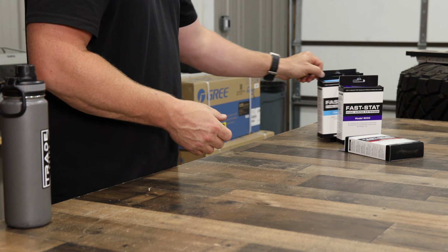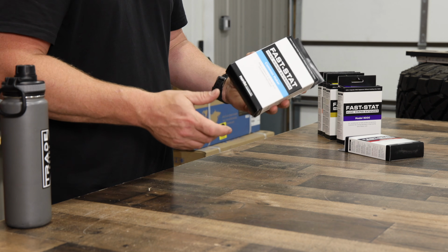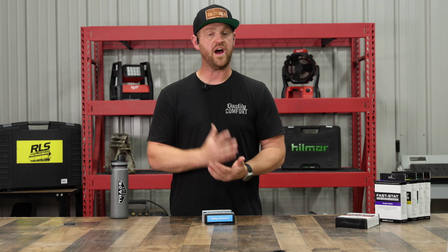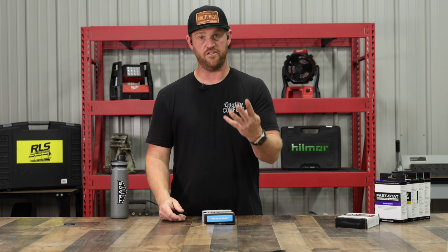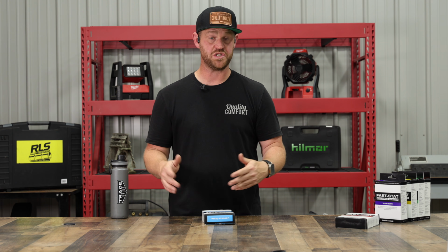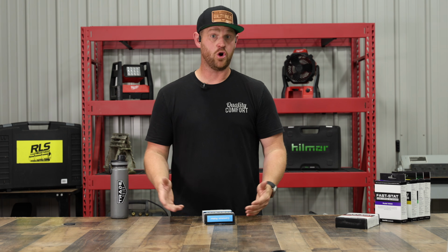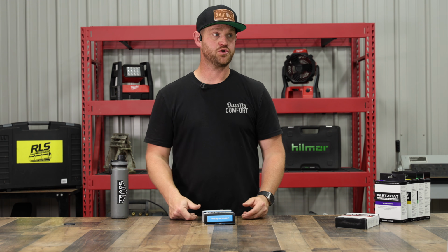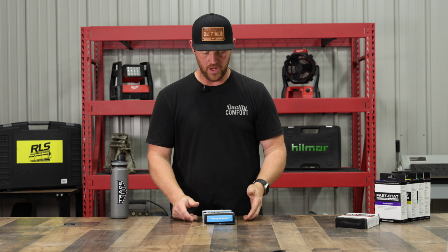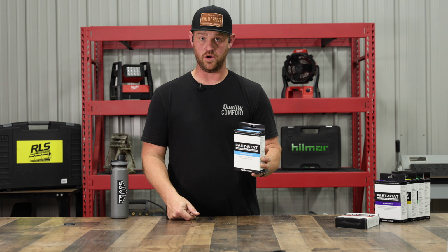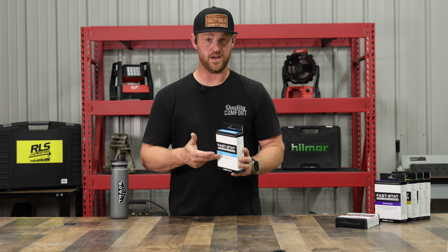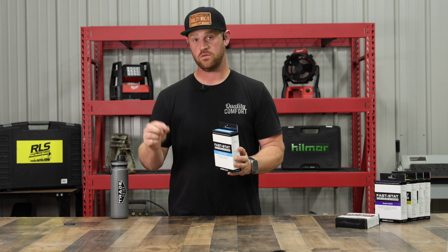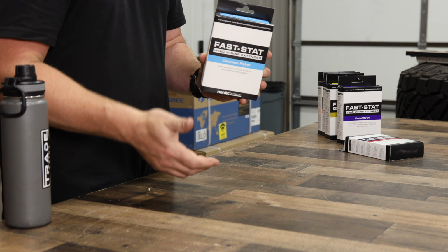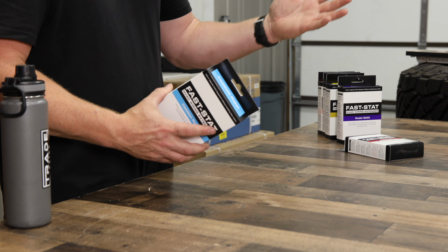Now, another way that we could use the FastStat, let's say a customer wants to install a Wi-Fi based thermostat that needs a common wire to operate properly. And you only have a 4-wire or a 5-wire, whatever the situation is, and you need 1 more wire. Well, normally you wouldn't be able to do it, right? You would have to try to figure out how to steal a wire somehow. Well, they have what's called the common maker. And that's all that this one does, is gives you that extra wire, your common wire, to be able to hook up a Wi-Fi based thermostat and you're good to go.